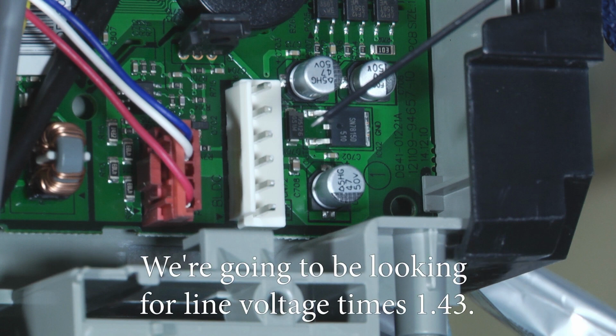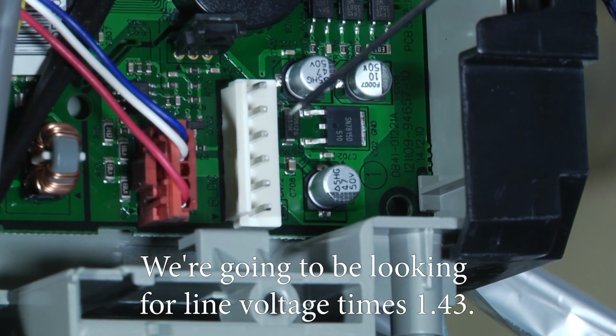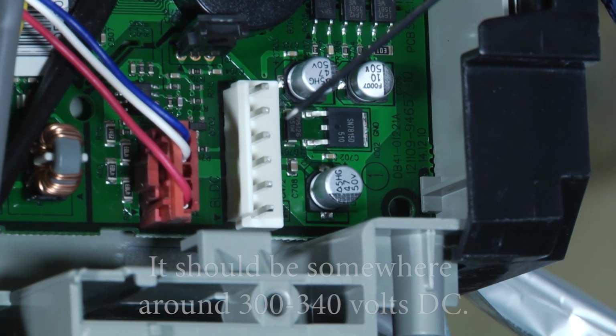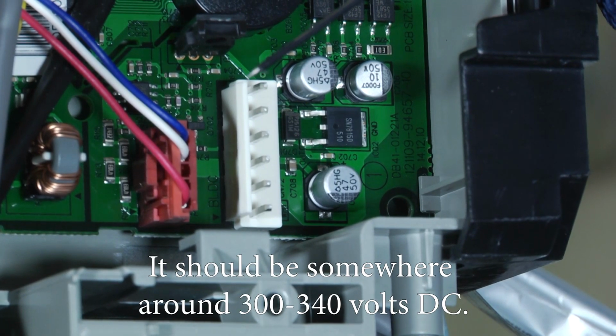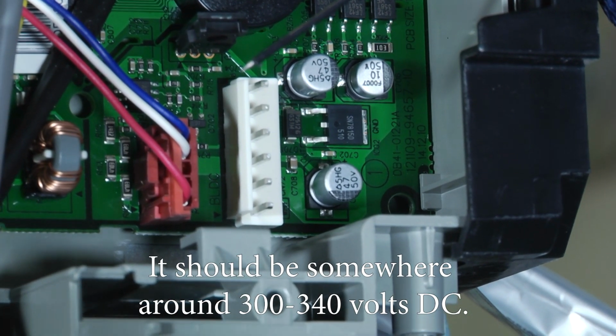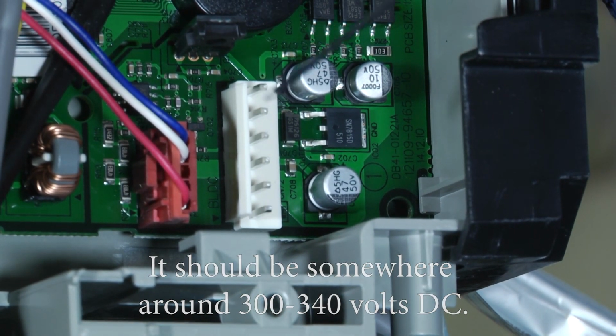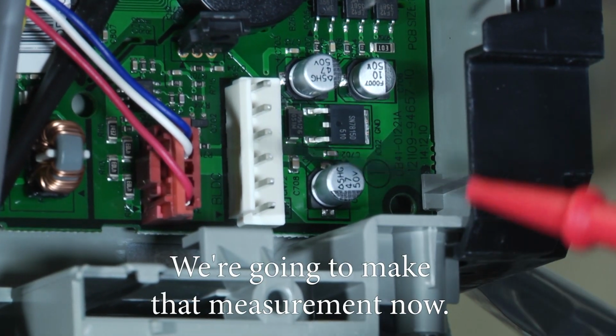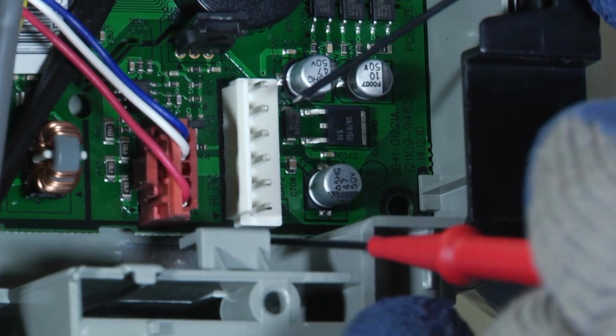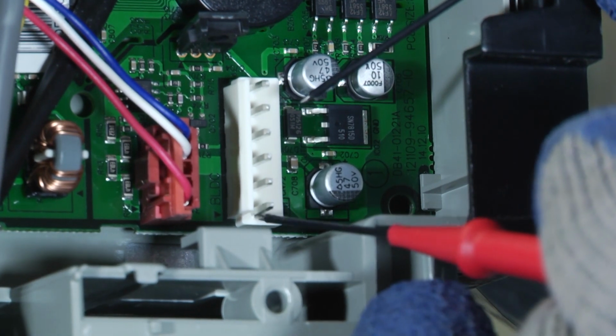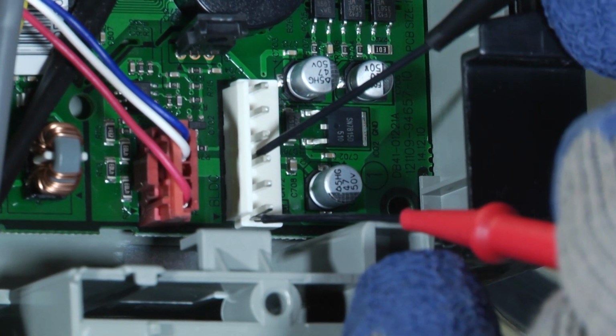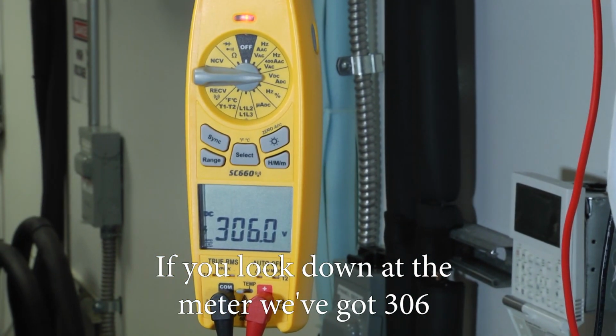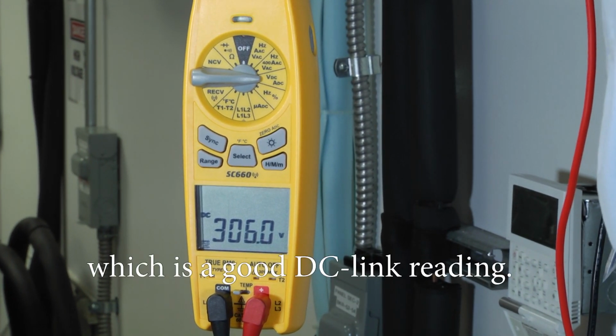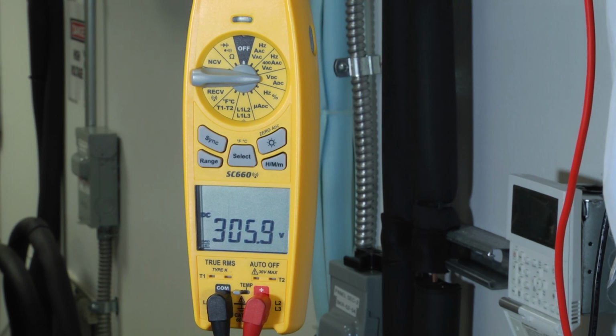We're going to be looking for line voltage times 1.43. It should be somewhere around 300 to 340 volts DC. So we're going to make that measurement now. If you look down at the meter, we got 306, which is a good DC link reading.